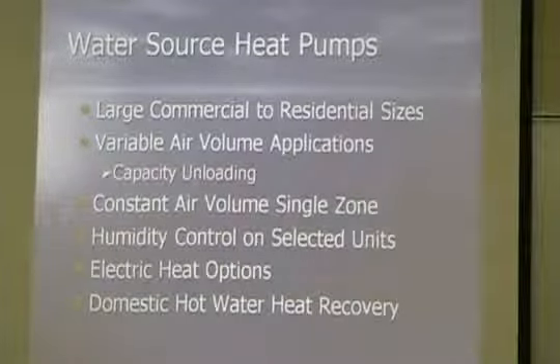For instance, this room right here, even though we've got a variable volume application in our building with an air handling unit, since this building is strictly interior and might need cooling in the wintertime, we put an individual heat pump in this room so that it's taking water off the loop. You can either heat or cool independently of anything else in the building. Humidity control, one manufacturer uses hot gas bypass from the compressor.